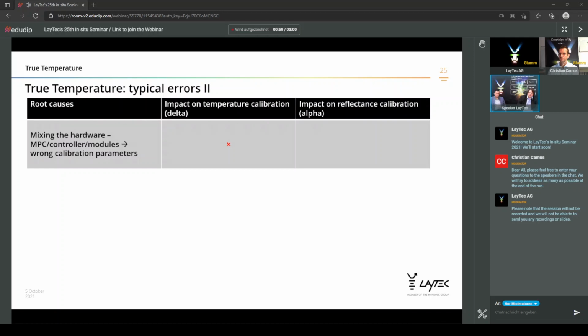And this will, in the first place, lead to wrong calibration parameters being active for that combination of system hardware. Because you must keep in mind that the entire system, as it is shipped from LayTec, is calibrated to its dedicated hardware and components and even software components, including calibration parameters, configuration files, and additional meta information in the system. Once you mix those units or even configuration data, it will immediately destroy the consistency of the EPIC-FTT system. Furthermore, if you do this on newer systems which are still under warranty, please be aware that this will immediately void any warranty of the affected systems.